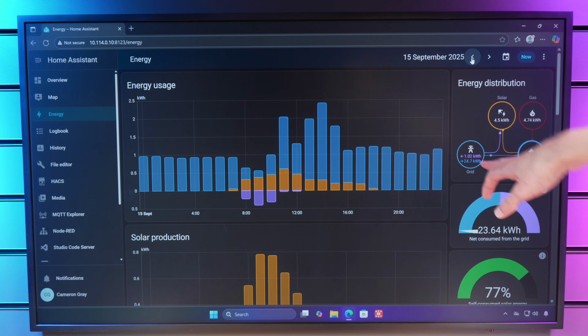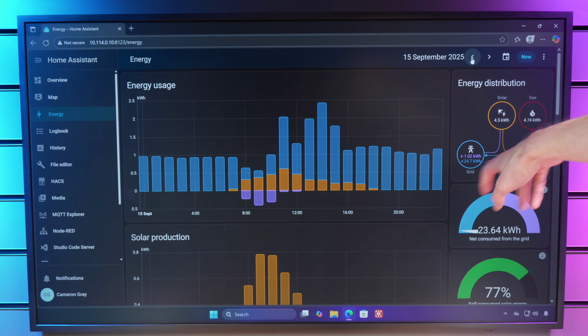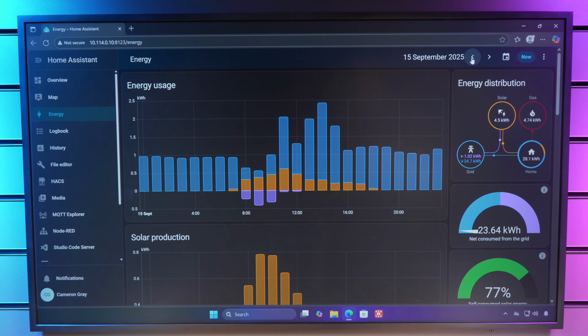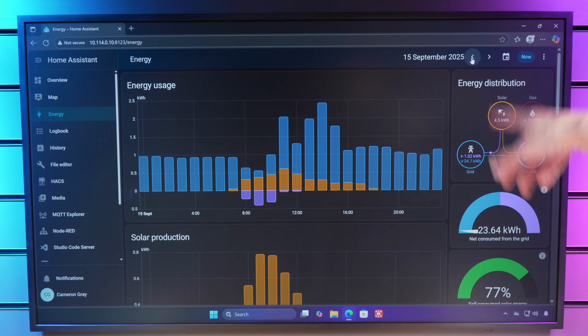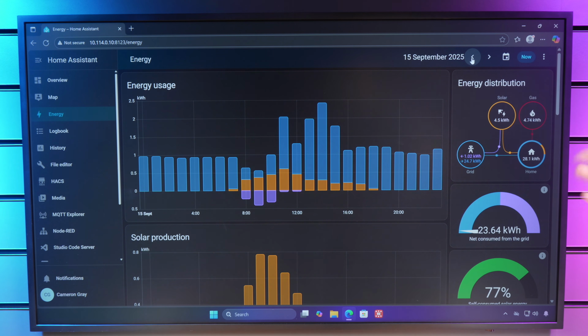And with this, it's saying I imported 24.7 kilowatt hours from the grid and exported 1.02. Whereas in actual fact, I imported 19.5 kilowatt hours from the grid, so close to 5 kilowatt hours less than this is reporting, and I only exported 0.5 kilowatt hours compared to the 1 this is reporting. So as you can see, before I did that without the CTs doubled up, I massively overcounted the amount of energy I actually imported and exported from the grid, which isn't right.